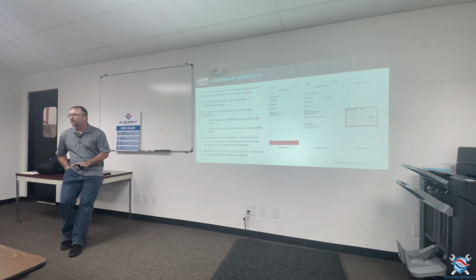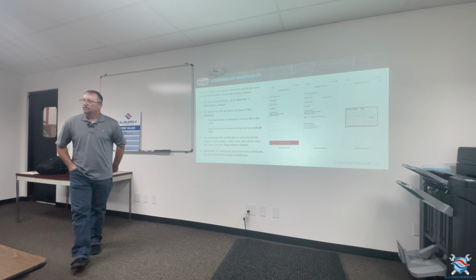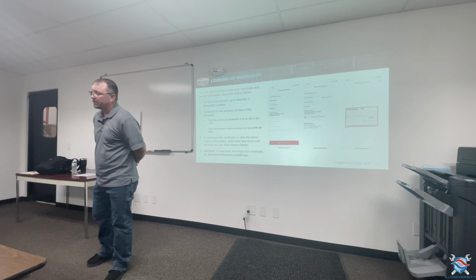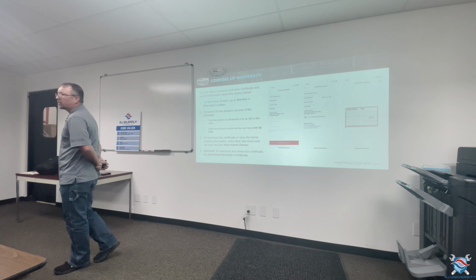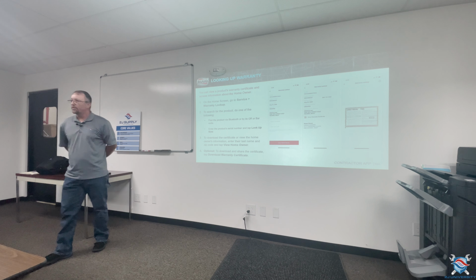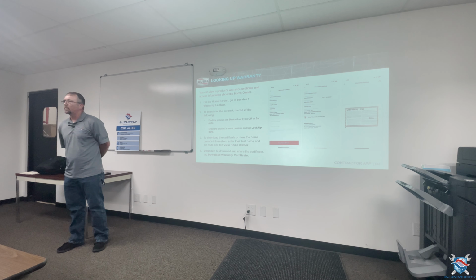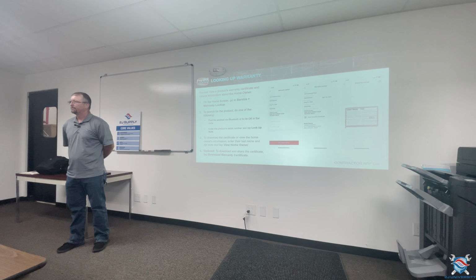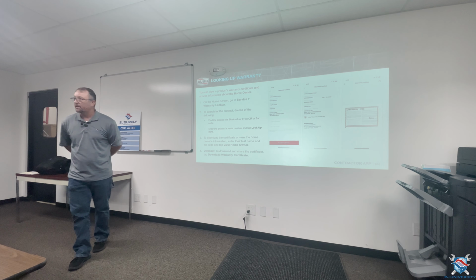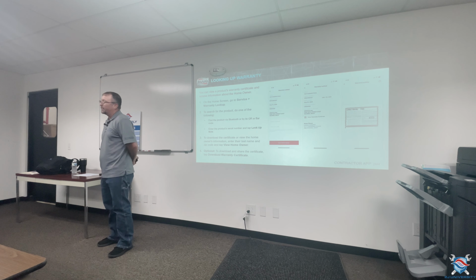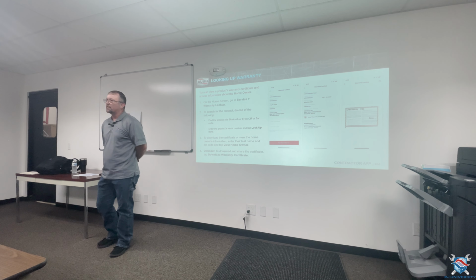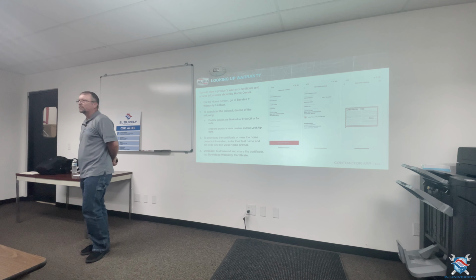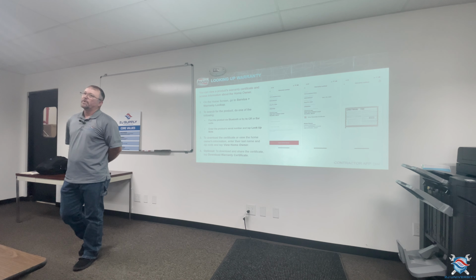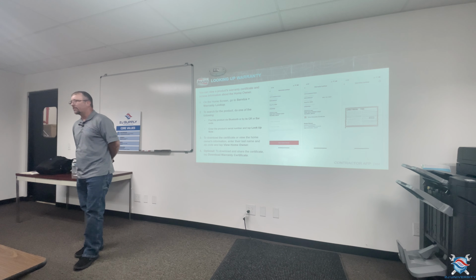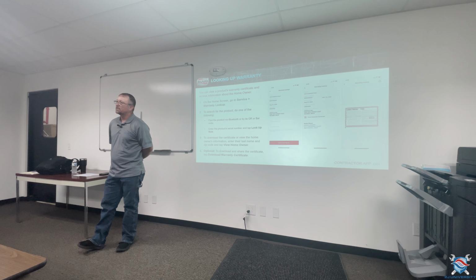Extended. You get standard 5. You're going to get standard 5 regardless. This is just for if you're trying to register it for warranty, it will kick back if you do not have it as an AHRI match or a complete system on a heat pump. Okay? ACs, like I said, standalone 13, 14 SEER can still be registered. They're just basic single stage units, so not too much you can hurt on those.